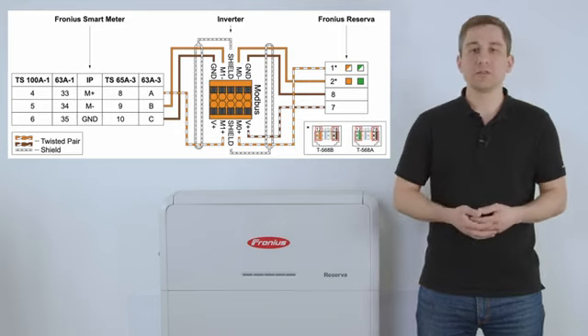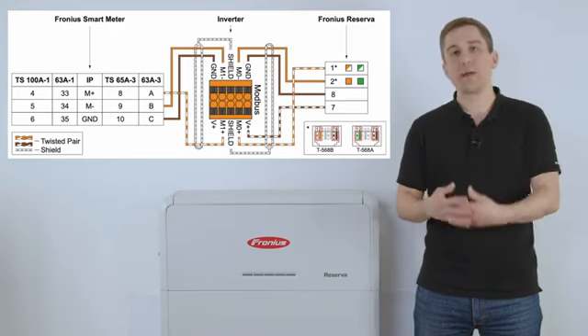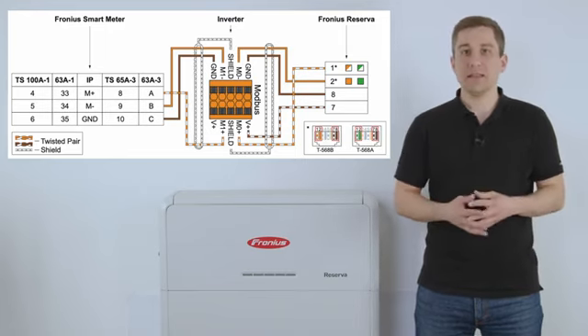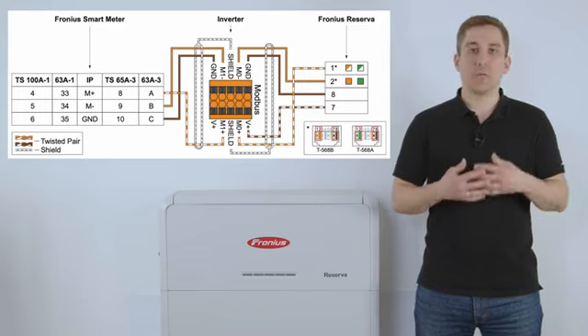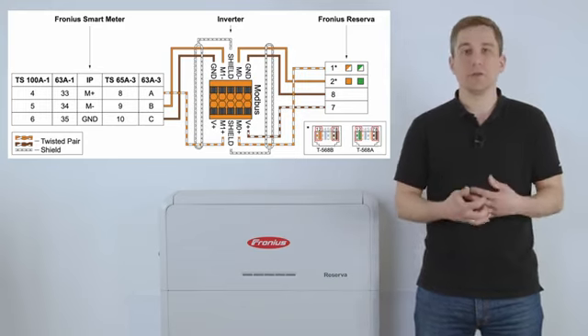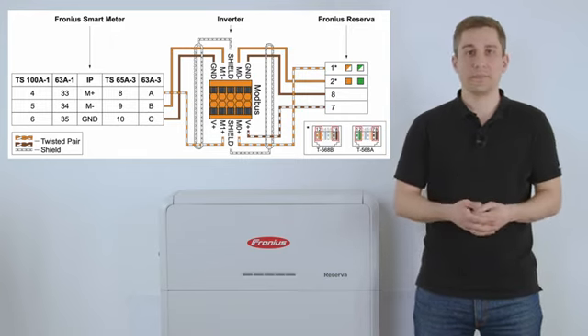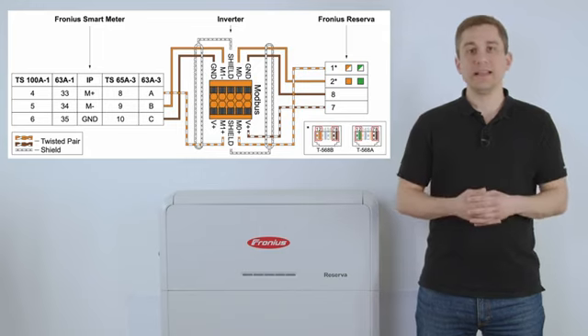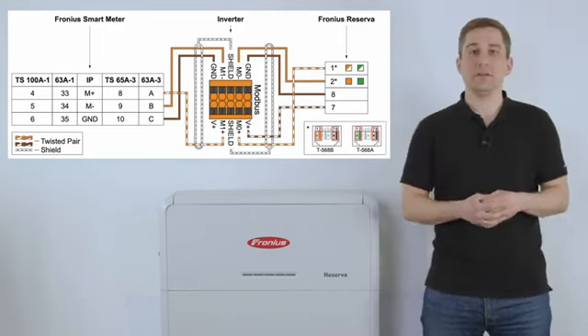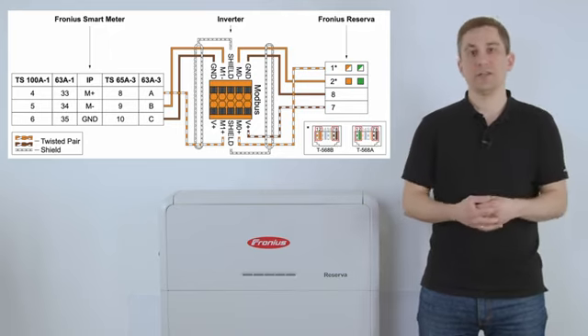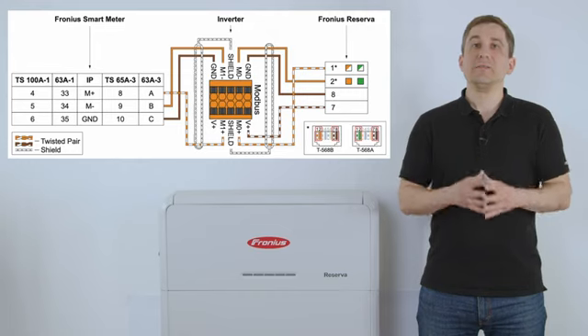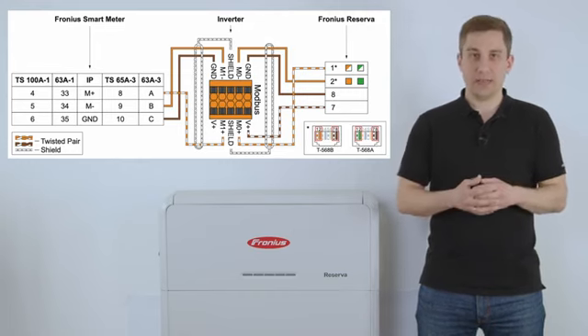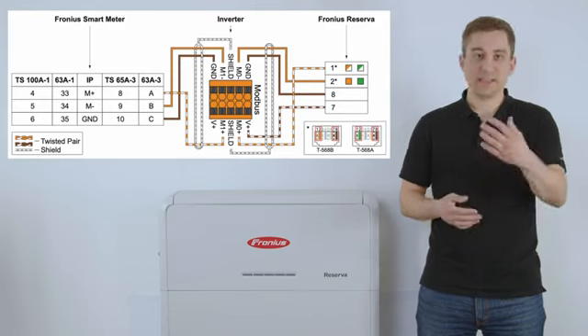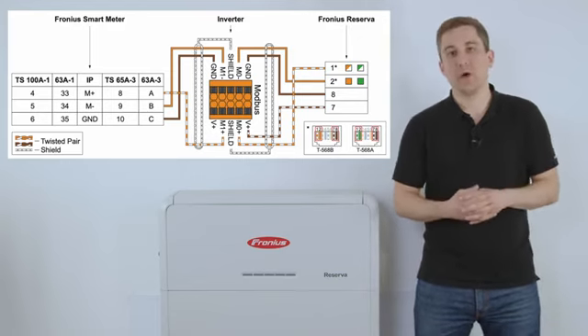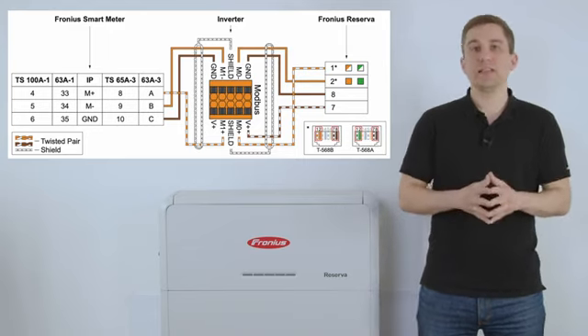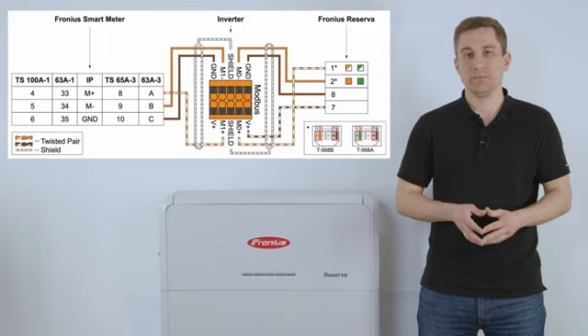please make sure to either use the orange and orange-white cable or the green and green-white cable from the Ethernet cable to install it to our Modbus 0 Plus and Modbus 0 Minus cable on the Modbus connector of the pilot device. Together with the voltage plus signal as well as the ground contactor, you can now cable the data communication to the Fronius Reserva and to the Gen 24 Plus inverter. After that, please also note to use the shielding of the cable and unisolate it on one side, in this case on the inverter, and use our shield contactor on the Modbus plug to make sure that the shielding of the cable is grounded on one side of the cable.